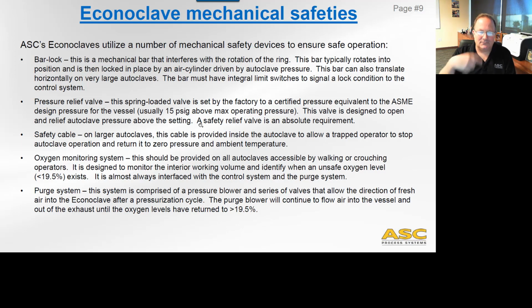Safety cable on large autoclaves. This is a cable, it's often called man inside alarm, and that's no longer used because there are women in autoclaves too, but this cable is provided inside the autoclave to allow a trapped operator to stop the autoclave operation and return to zero pressure and ambient temperatures. So that's a safety system that if someone gets into trouble, they're going to pull that thing and big alarms go off and everything happens like that.